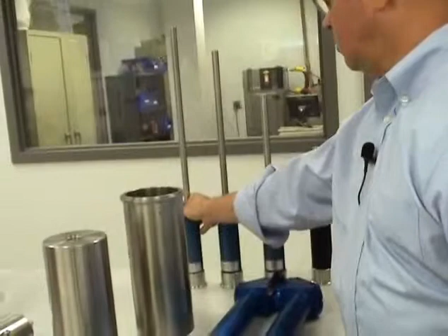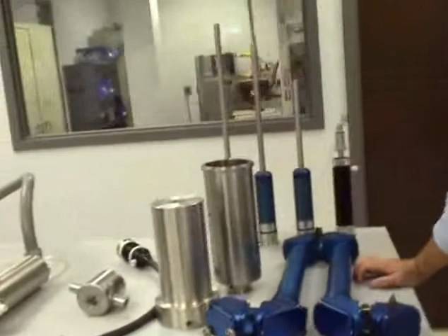And you mentioned, obviously, depending on the chemistry that you want to look for, this type of sensor material that you would use. But what kind of temperature and pressure could I use these at? The pressure and temperature range varies depending on the type of sampling technology that you have. These probes here come in a standard version, which is 7 bar, and the temperature rating is minus 80 to 200 degrees C. There's a high pressure version of these probes, which has the same temperature rating, minus 80 to 200 C, but the pressure rating is up to 100 bar.